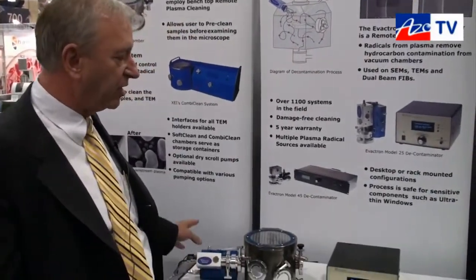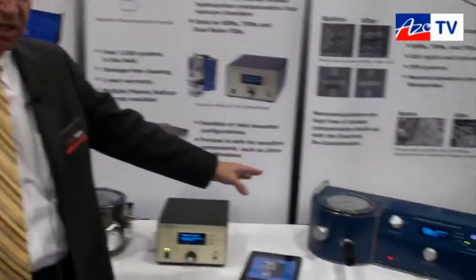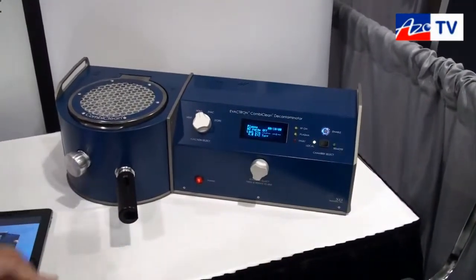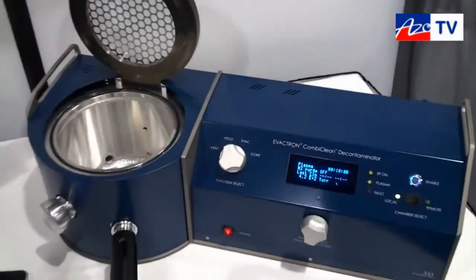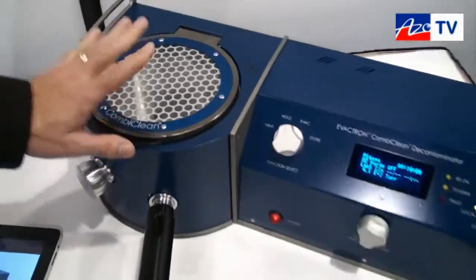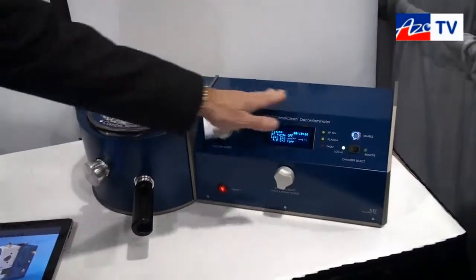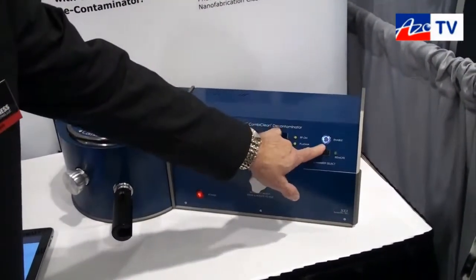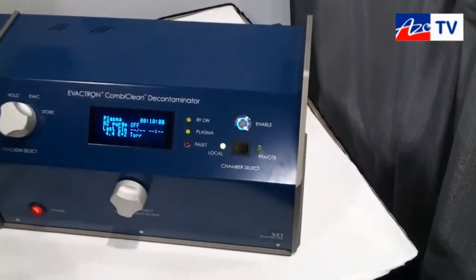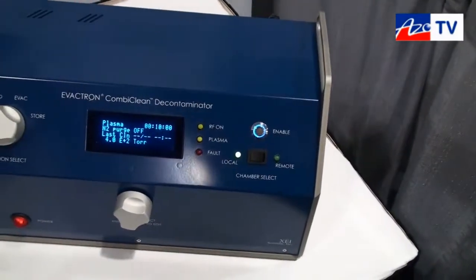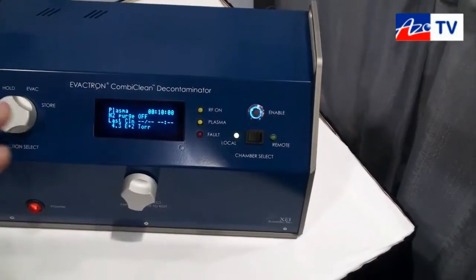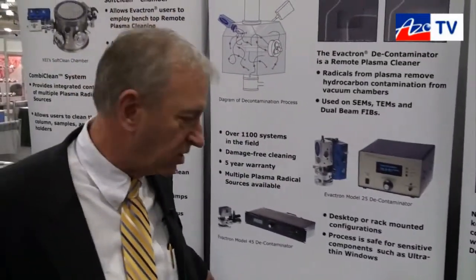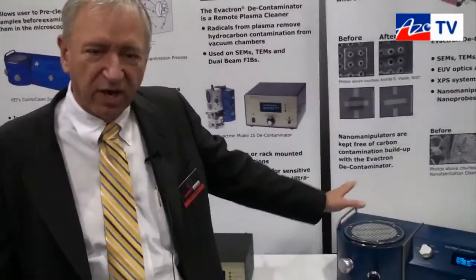We can go from that system to something that's even newer today, and that's a combined system. This is our CombiClean, and the CombiClean will allow you to insert your transmission electron microscope holders and samples, or open the chamber and put your specimens in here and clean them. The difference here is that there are two plasma radical sources — an integrated internal plasma radical source — but there's a simple switch that allows us to go between a remote and a local state. So we're driving more than one plasma radical source with one system, which is very cost effective. The combined system is about $35,000.